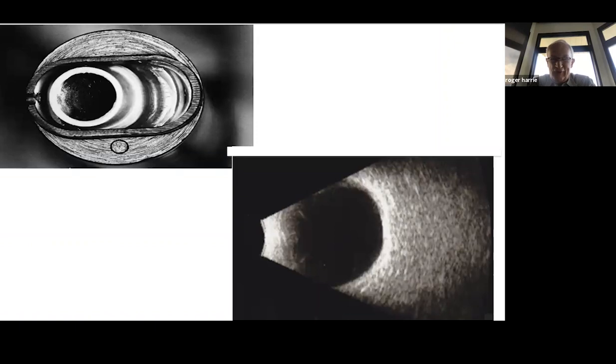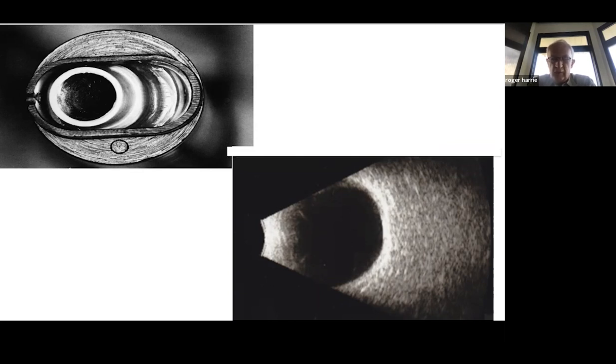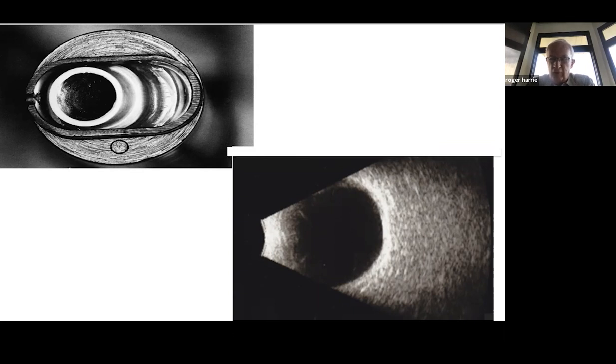At the tip of the probe — whether A or B-scan — there is a very thin quartz crystal. An electrical pulse stimulates that crystal to vibrate, generating the ultrasound. The same crystal is then dampened electronically within thousandths of a second; when the returning sound wave hits it, the crystal vibrates again, and that vibration is picked up as an electrical signal.